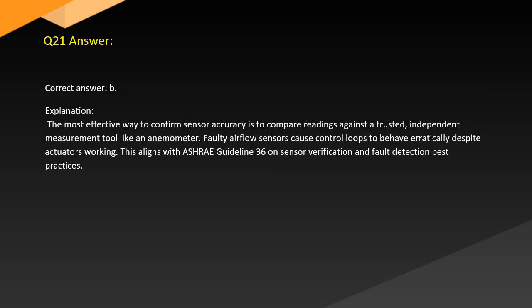Answer. Correct answer: B. Explanation. The most effective way to confirm sensor accuracy is to compare readings against a trusted, independent measurement tool like an anemometer. Faulty airflow sensors cause control loops to behave erratically despite actuators working. This aligns with ASHRAE Guideline 36 on sensor verification and fault detection best practices.